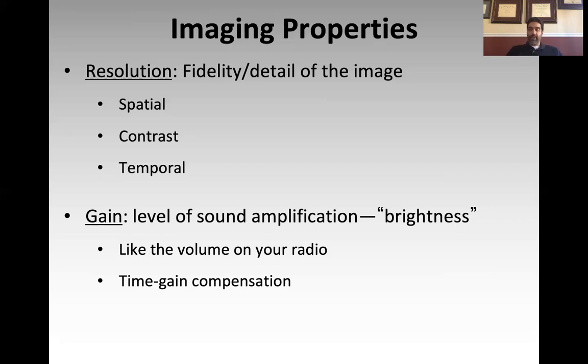It's similar to ultrasonography. The mistake I see a lot of novice sonographers make is: they put the probe down, see a crappy image, and think they need to make it better, so the first thing they do is jack up the gain. It's not going to work — it's just going to make that crappy image brighter. What you need to do is tune into your station first. Optimize your imaging first, and then optimize your gain.